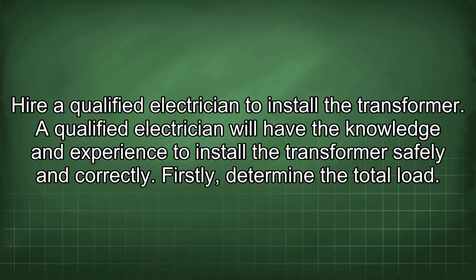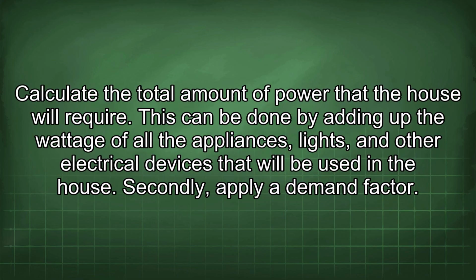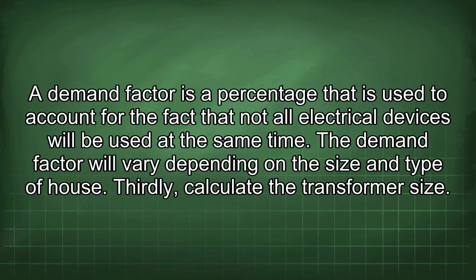Firstly, determine the total load. Calculate the total amount of power that the house will require. This can be done by adding up the wattage of all the appliances, lights, and other electrical devices that will be used in the house. Secondly, apply a demand factor. A demand factor is a percentage that is used to account for the fact that not all electrical devices will be used at the same time.